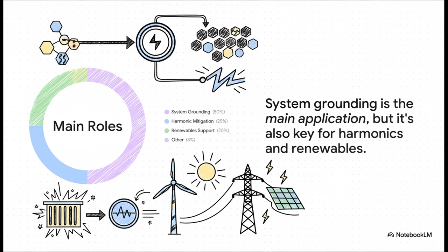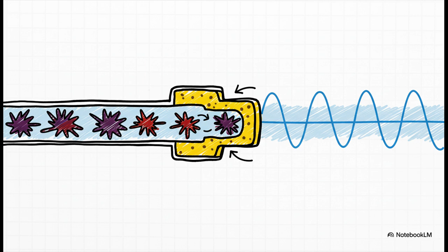Now, this is seriously cool. That same zigzag winding is incredibly good at trapping specific kinds of electrical distortion, what they call triple harmonics. These are nasty currents, often created by our modern electronics, that can make transformers overheat and equipment fail. The zigzag transformer acts like a sponge, soaking them all up before they can pollute the rest of the grid.